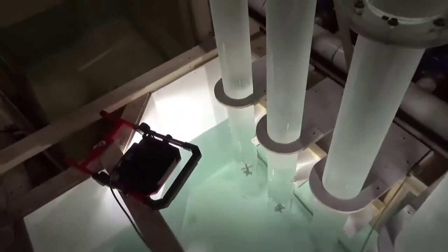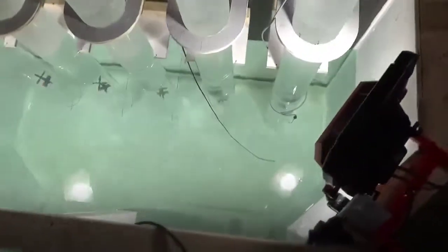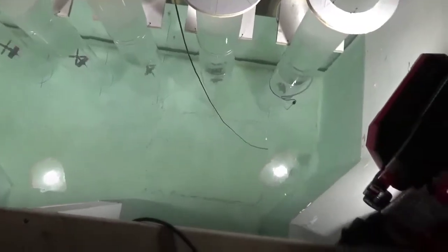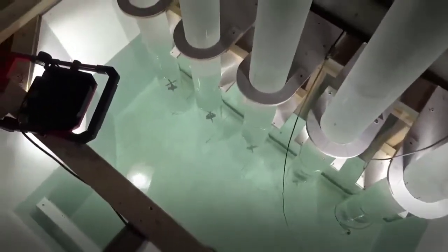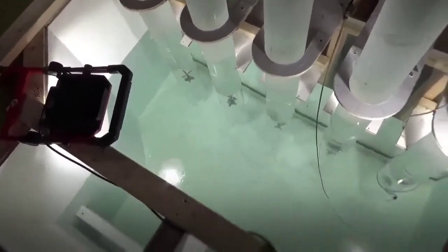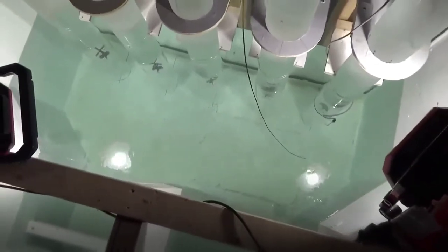The expansion, the flared walls on the side are really what set conditions up. No dividing walls down here. We've got a lot of flow separation as our water comes out of these expansions right here, and that's creating significant pre-swirl. So we'll go down and take a look at that in a minute. Before we do, we're going to put a little bit of dye in up here.